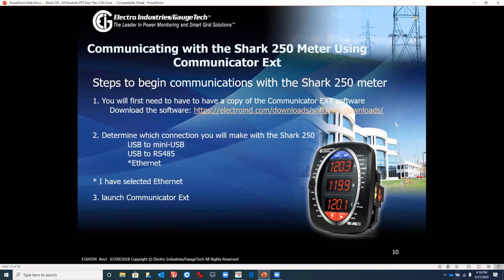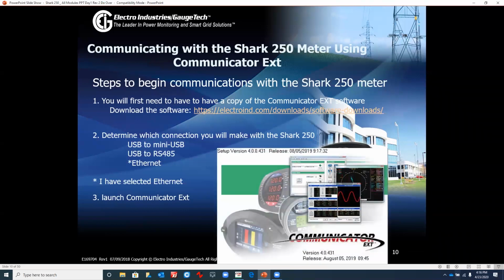Note the meter does default to IP address 10.0.0.2, subnet mask 255.255.255.0, a Class C address. You would have to set up something similar on your laptop computer, on the same network, except the host address at the end would be anything other than .2. So let's launch Communicator EXT.